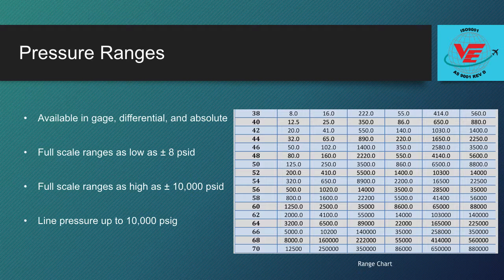The P365 is also available in pressure ranges as high as 0 to 10,000 psi, and these can be used to measure extreme hydraulic pressures. Although there are 17 different full-scale pressure ranges for the P365, from plus or minus 8 psi differential all the way up to plus or minus 10,000 psi differential, the P365 can also measure gauge pressures as high as 10,000 psig. Every P365 can withstand static line pressures of up to 10,000 psi on both ports. This means a low-range P365 can be used to measure small pressure drops in a high-pressure system.